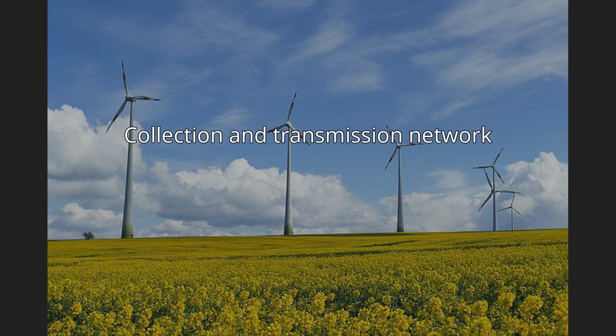In a wind farm, individual turbines are interconnected with a medium voltage, usually 34.5 kV power collection system and communications network. At a substation, this medium voltage electric current is increased in voltage with a transformer for connection to the high voltage electric power transmission system. A transmission line is required to bring the generated power to often remote markets. For an offshore station, this may require a submarine cable. Construction of a new high-voltage line may be too costly for the wind resource alone, but wind sites may take advantage of lines already installed for conventional fuel generation.